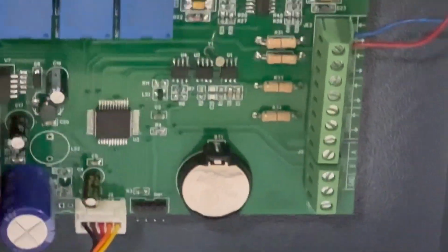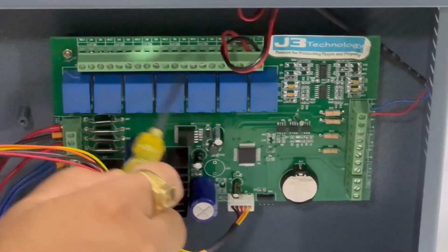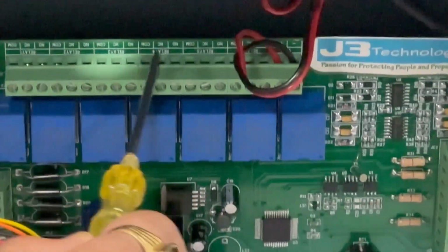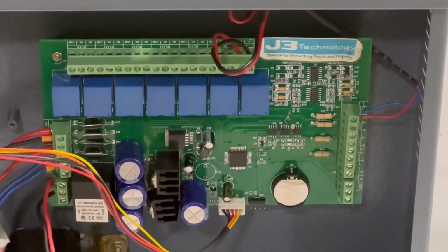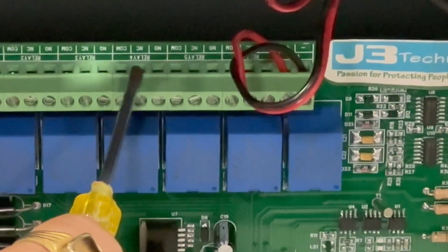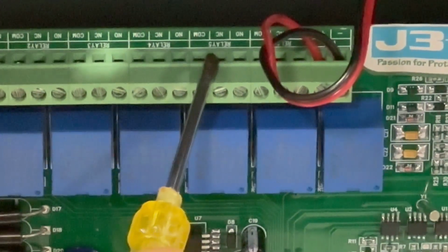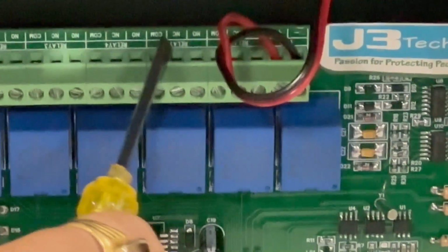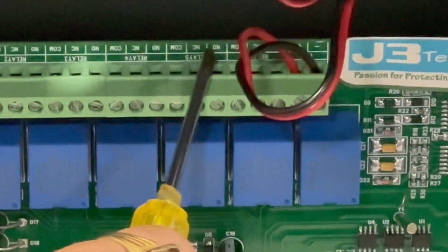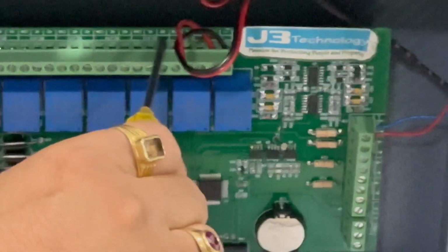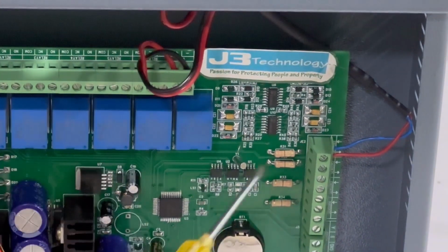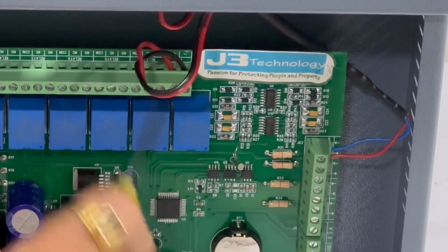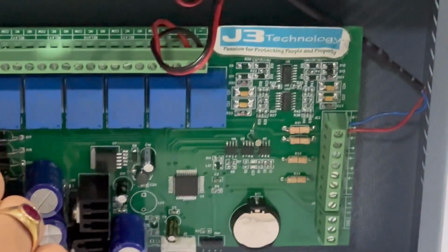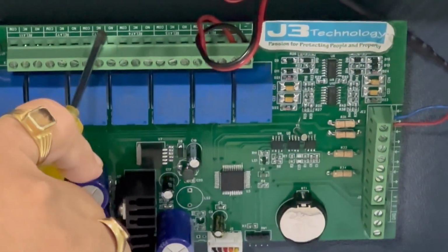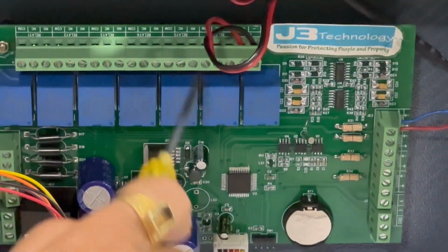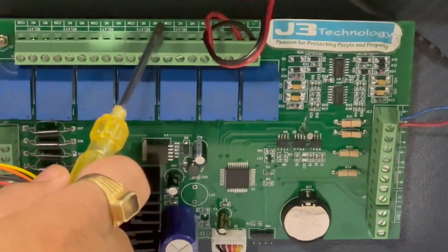Again, there is an individual relay contact for each zone: zone 1 relay contact, zone 2, zone 3, zone 4 relay contact. And you will also get the common fault and common alarm relay over here. This is a fault relay and this is a common alarm relay. Whenever there is an alarm in any zone, the NO/NC contact of this relay will change, and whenever there is a fault in any zone, the fault relay will change. In this case, individual zone dry contacts are also provided to the client according to their use, along with the common relay and the common fault relay, so they can use them according to their convenience.